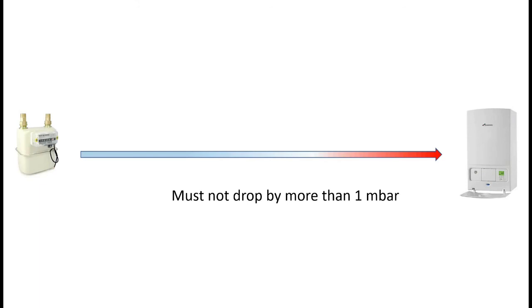Now the law states that you must not have a drop of more than one millibar between the metre and the appliance. So if the pressure at the metre is 21 millibars, the minimum pressure you're allowed at the appliance is 20 millibars. Correct pipe sizing will ensure that you get no more of a drop than one millibar.